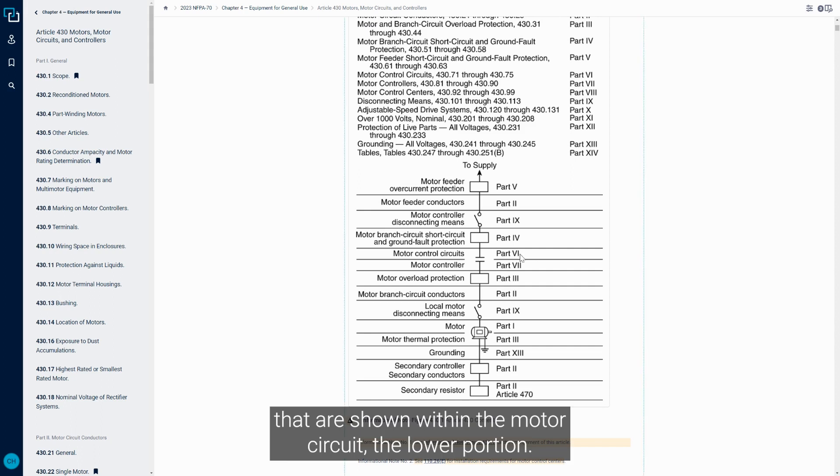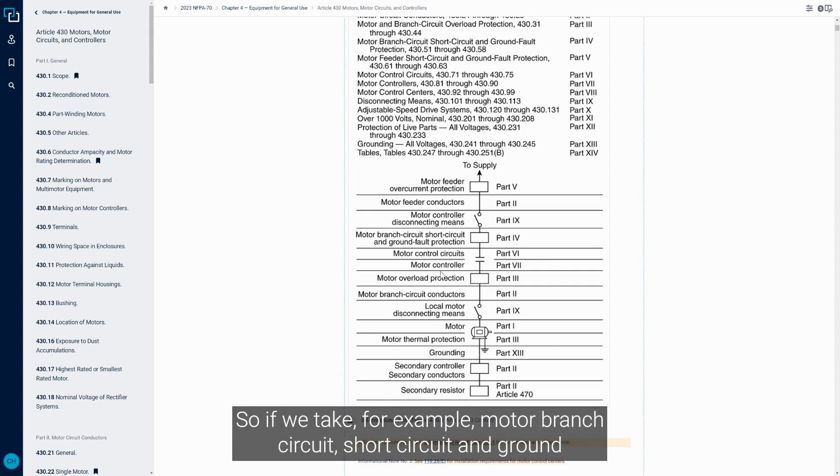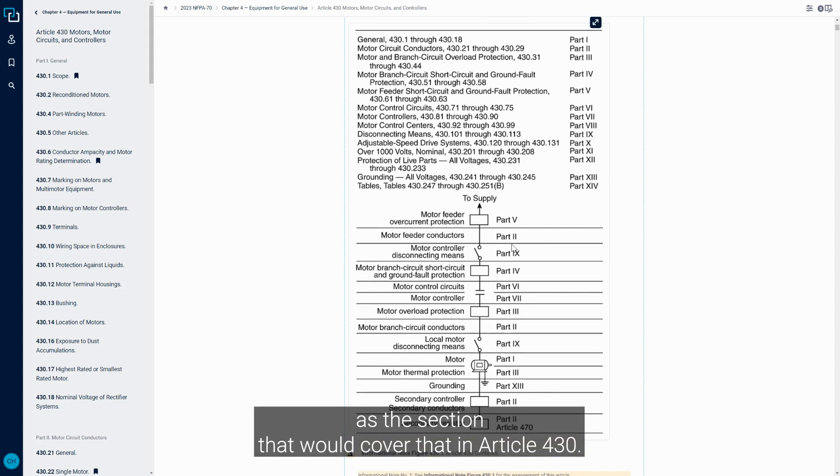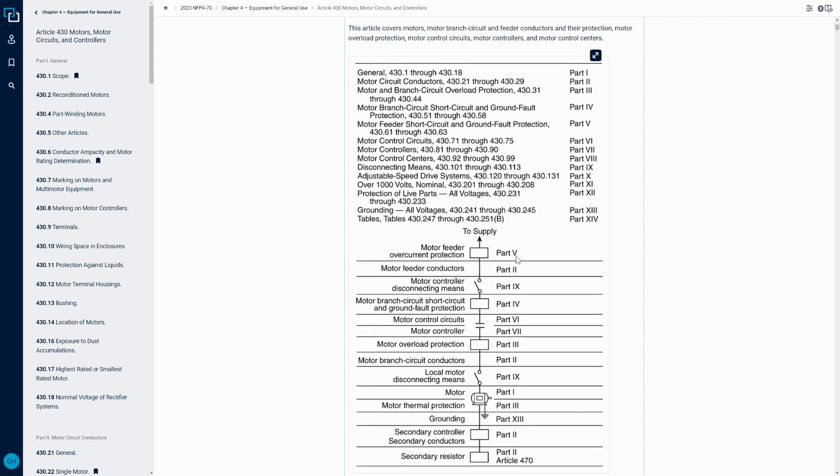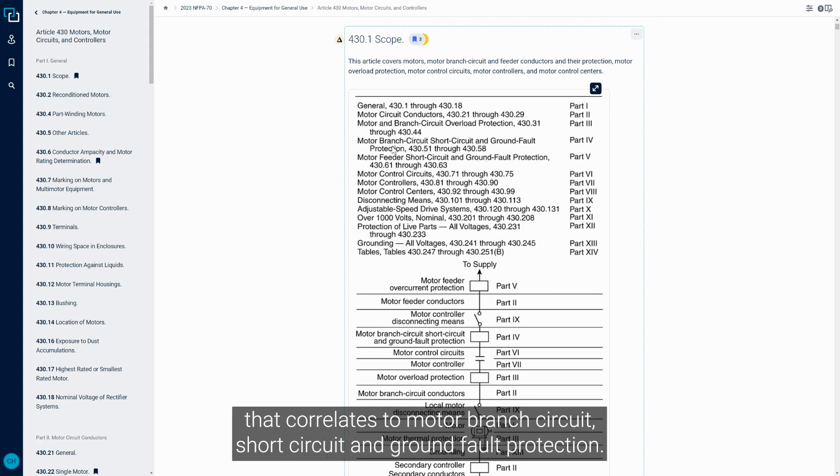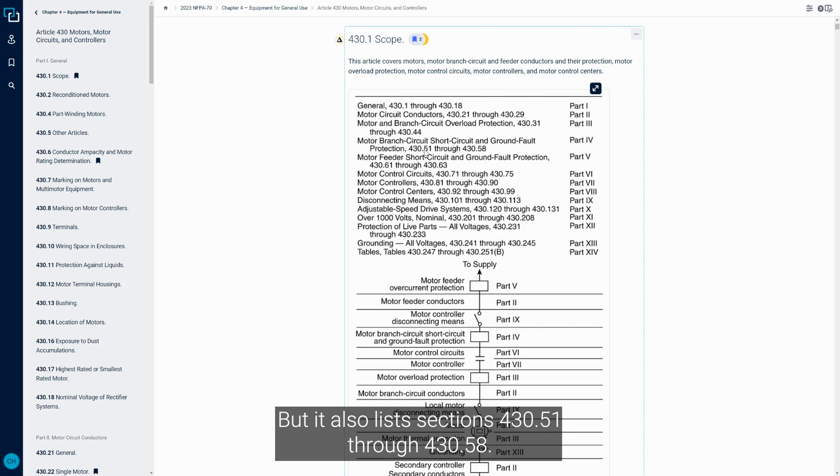The lower portion of Figure 430 is very similar to a schematic diagram in the parts shown within the motor circuit. If we take, for example, motor branch circuit short circuit and ground fault protection, it gives us Part 4 as the section that would cover that in Article 430.